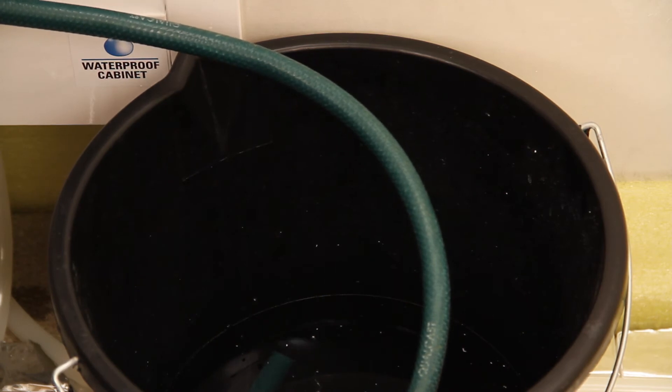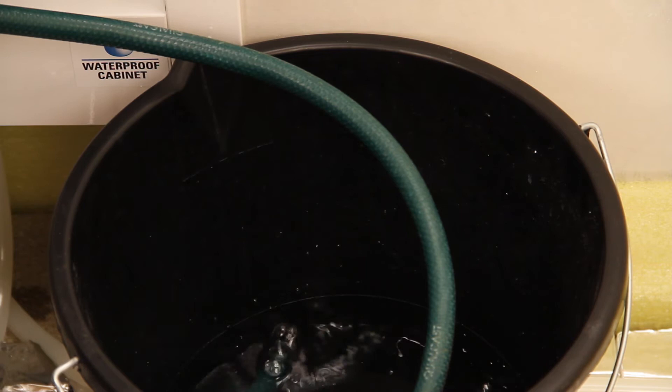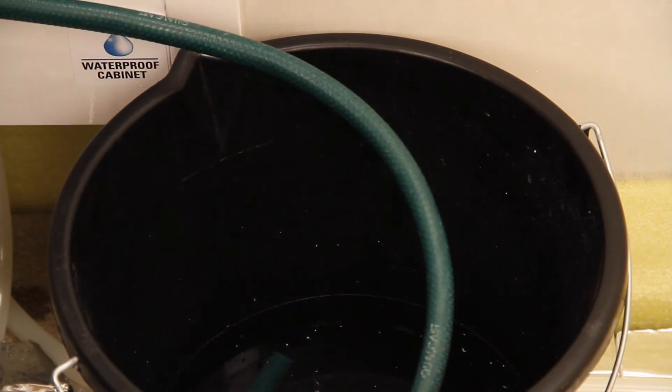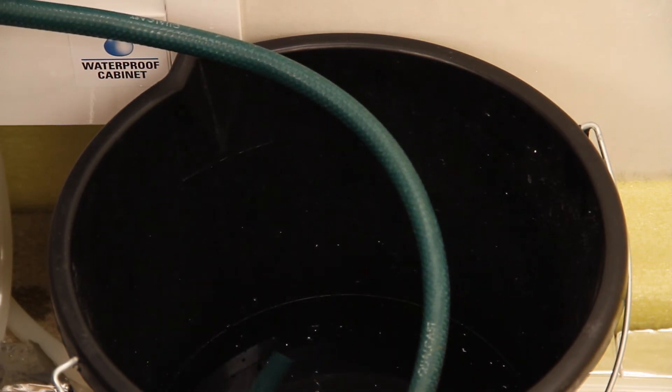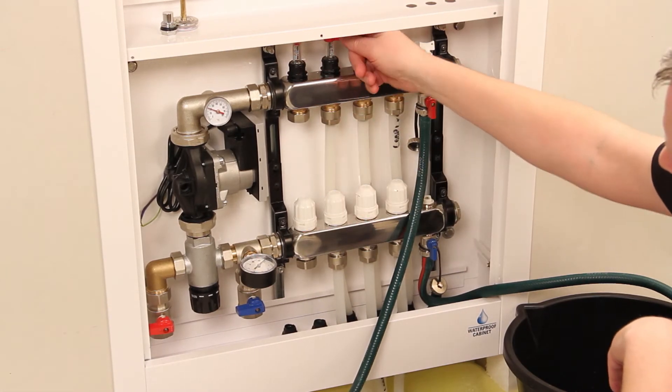Make sure that the drain hose is directed into the bucket, air will pass through the pipe and show as bubbles in the water. When the water runs clear, close the manual return valve and corresponding flow gauge. This will seal off that circuit.